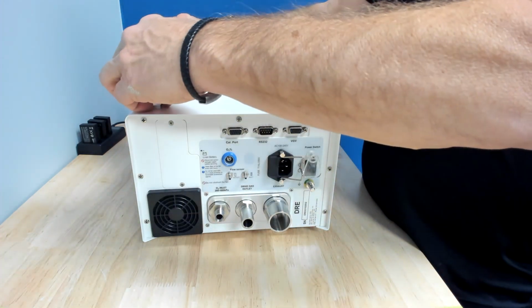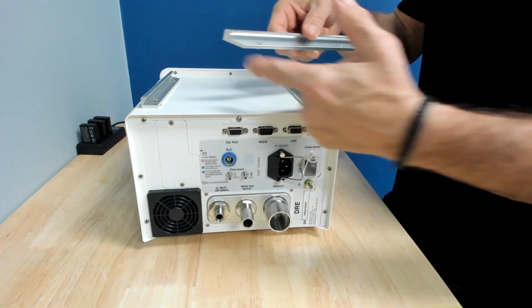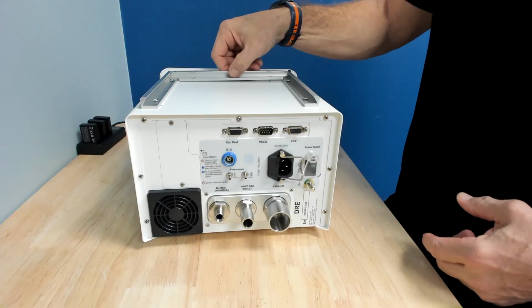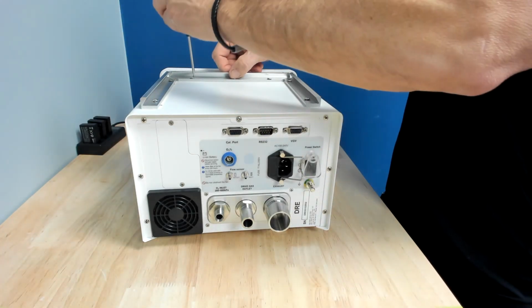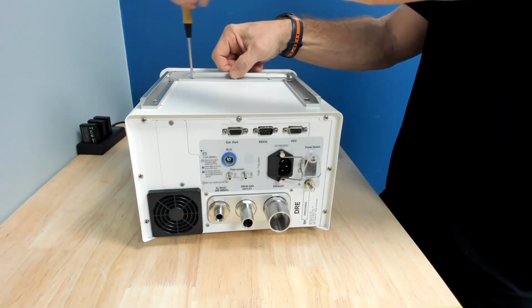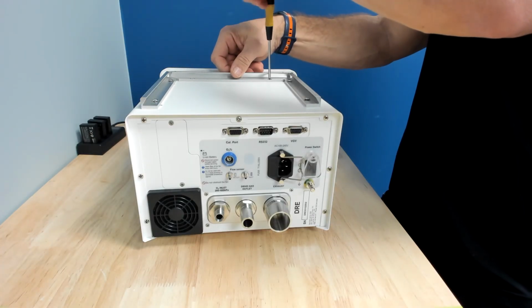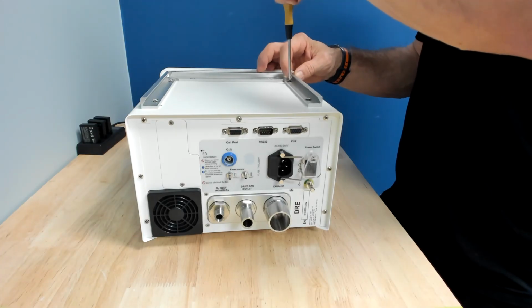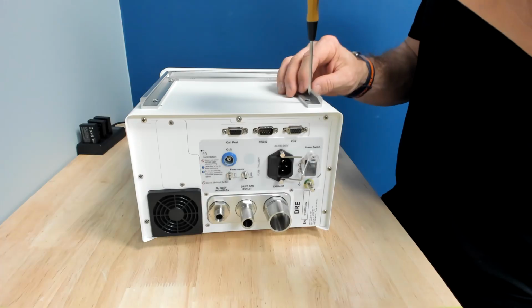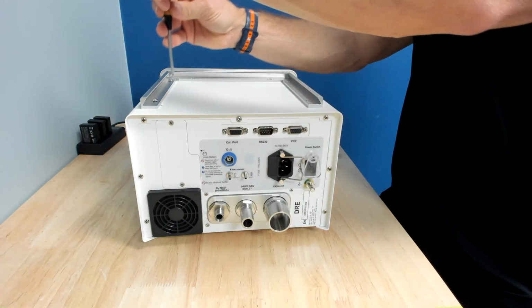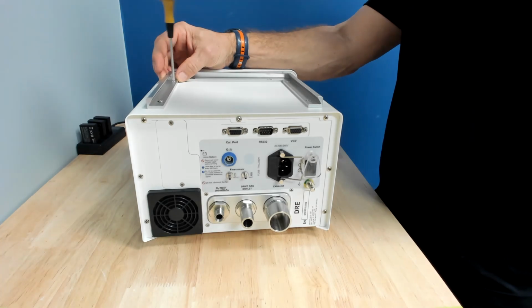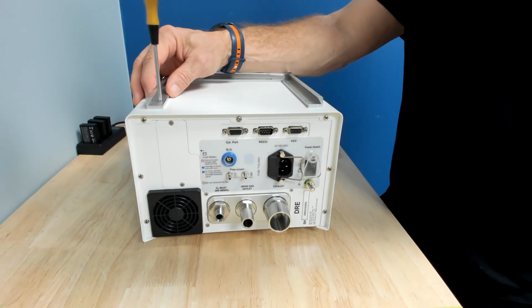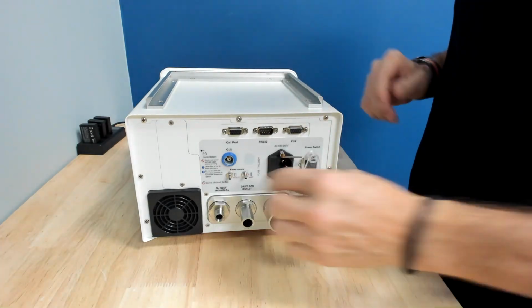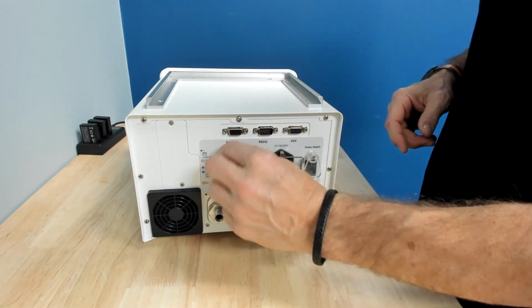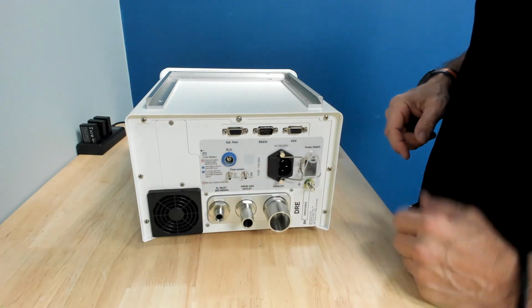So now we're going to go ahead and put the top bracket back on. One is, see if you're double angled, is the one that goes towards the front. And don't bear down on these. Just snug is good. So there's how to tighten up the ports, potentially replace the O2 receptacle.